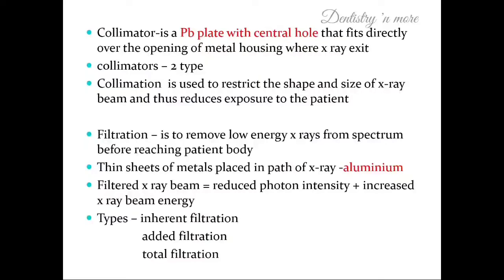Thus, it tries to reduce the exposure to the patient. So there are two types, that is the rectangular and the circular or the round ones. Rectangular collimators are more preferable because they try to limit the beam towards the image receptor size itself.